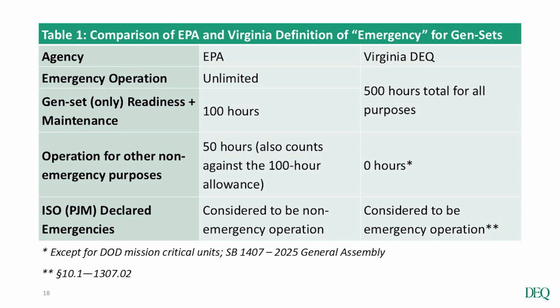And then we just have some differences with EPA here. Really the primary one is the row for operation for other non-emergency purposes. EPA's definition of emergency allows 50 hours per year for those kinds of operations or events, whereas in Virginia we allow 0 hours for that, with one exception, and that exception was put in place again by the General Assembly back in 2025. That exception is for Department of Defense designated mission critical gensets. I have a little bit more about that on this next slide.